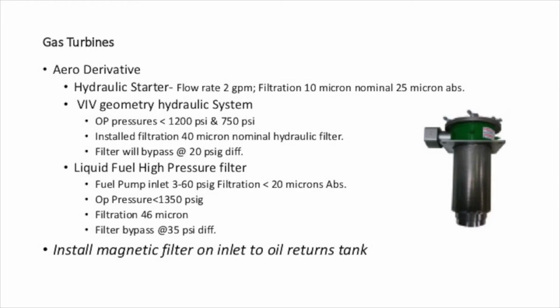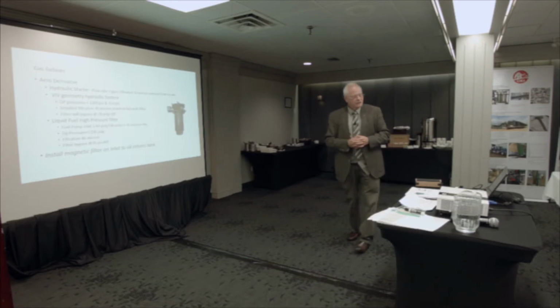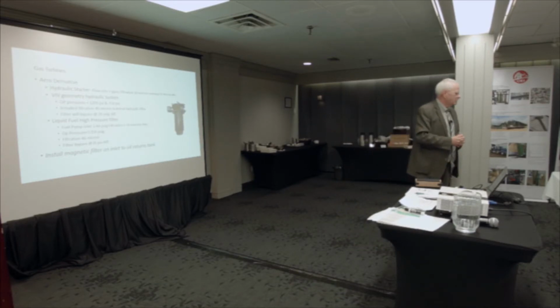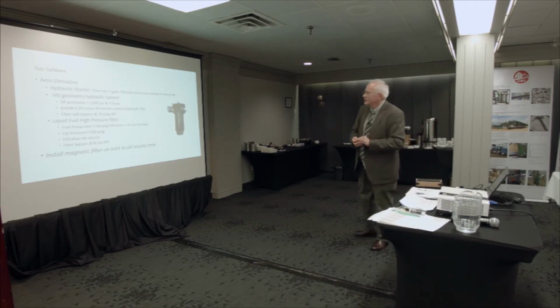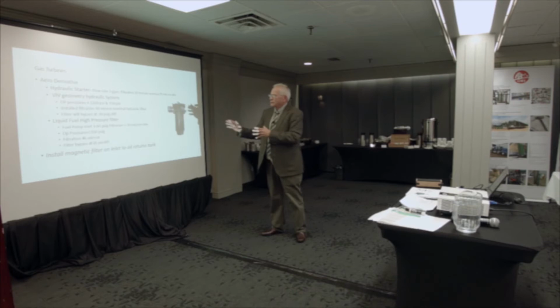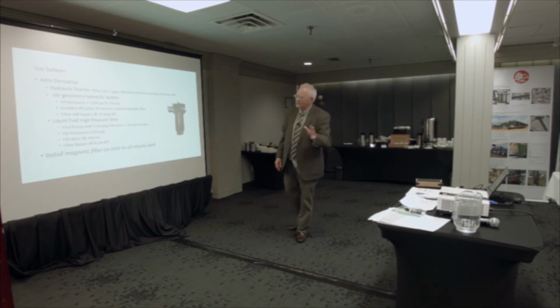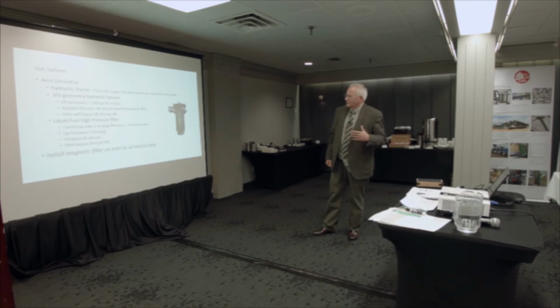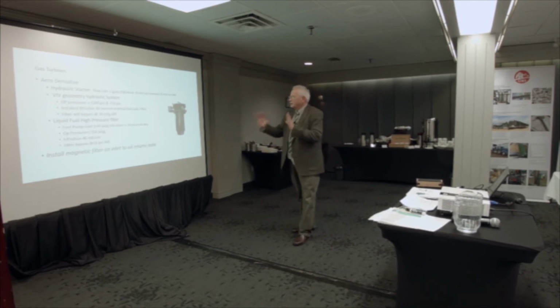So, gas turbines. As you've heard, they're going to be shutting down all the coal-fired generation over the next 20 years in Alberta. So we're going to have to anchor our system somewhere. We can't do it with solar, and we can't do it with wind turbines. So we're going to be going to gas turbines. And the steam turbines were very forgiving as far as maintenance and operating conditions compared to the new gas turbines. I use as an example an aeroderivative turbine. We installed about 10 of these throughout the world: United States, Canada, Australia. It's an aeroderivative, so I just wanted to go through it real quick.